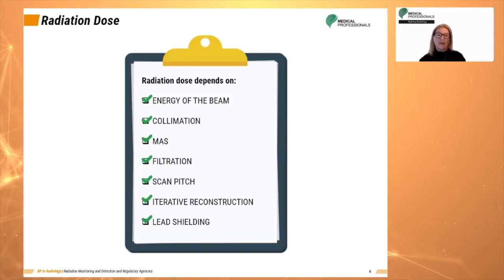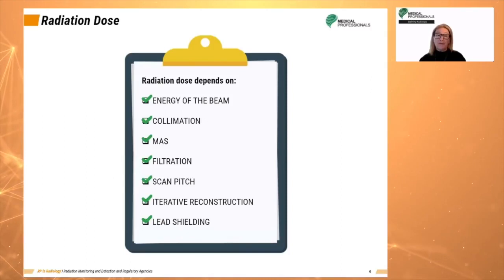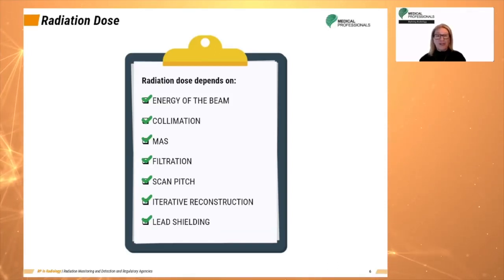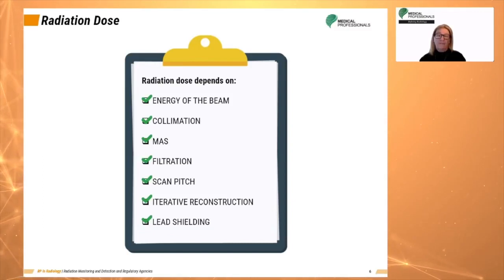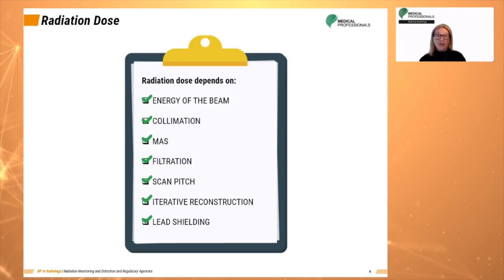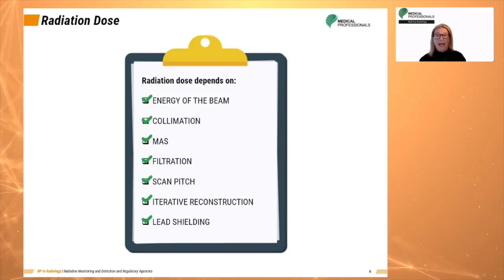The MAS is varied in order to perform each scan. More MAS is used to scan larger volumes of tissue or to compensate for thinner scan slices or tight collimation. Because CT is a computer-assisted technology, the effects of changes in MAS do not appear the same way as with conventional radiography. Instead, optimization in signal-to-noise ratio is sought. There are two purposes to filtration: skin dose reduction and reduction in certain kinds of artifacts that result from beam hardening.